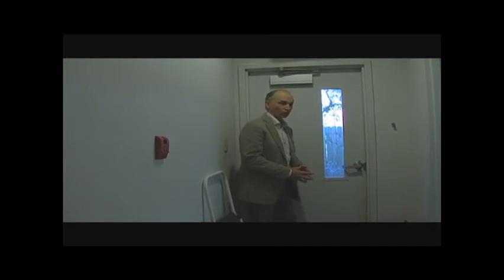This is what building science is doing. Here's the white door that was black. It's well gasketed and well sealed, but that really doesn't matter — if you don't have enough return air, we're going to cause problems with the door. The door feels cold to the touch because it's metal, though it is insulated. But the fact is, if you're constantly sucking on this door, you're going to pull that cold air in. A dew point is reached because of the cold metal, and when you reach a dew point, mold forms. If you have a big delta — a big difference in temperature and moisture — then mold can tend to form.